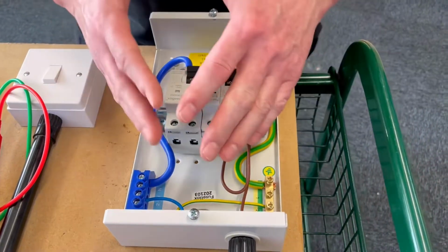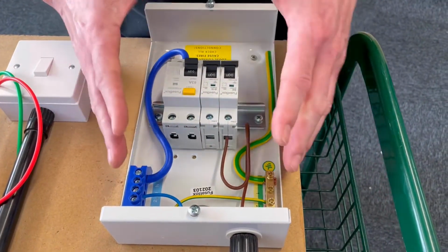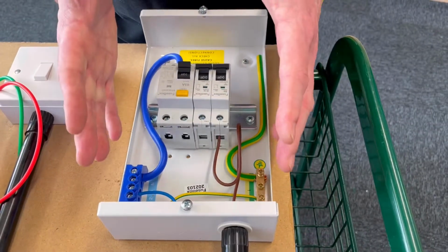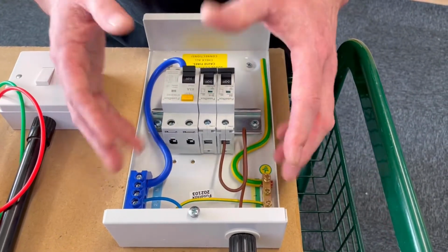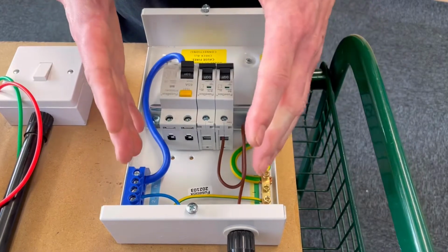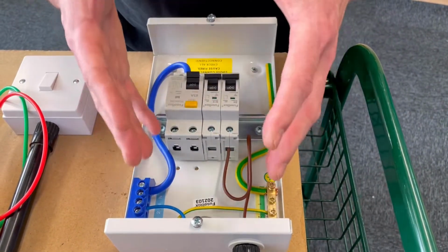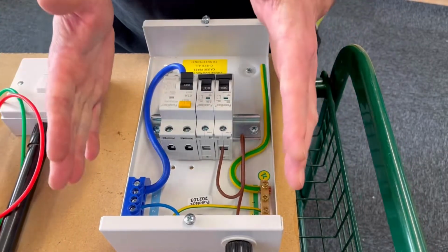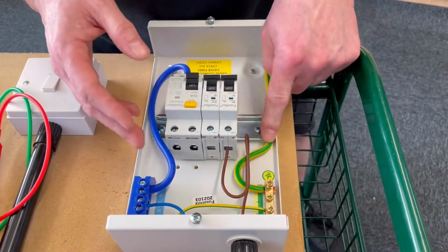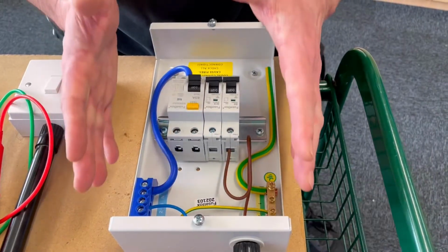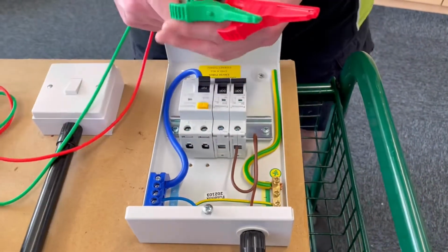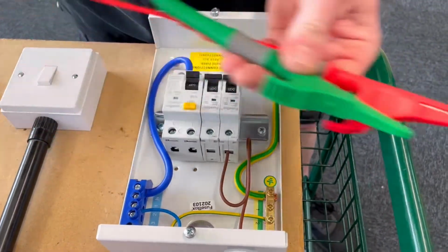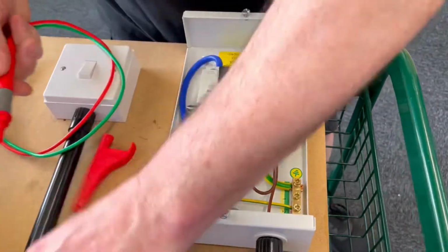I know at college that's probably not going to be the case, and you're not going to have these in place because obviously it's not connected to the electrical system. But the sooner you hear the fact that when you carry out your insulation resistance test, the earthing conductor and bonding conductors must be in place and connected when carrying out the test, it helps you move through your levels of understanding and knowledge. So I've left the earthing conductor in as if it's connected to the source earth for this test. There is no order in which to carry these out, not even a Gary order, so it doesn't matter which way around we do it. So I'm going to change one of these over for a probe.